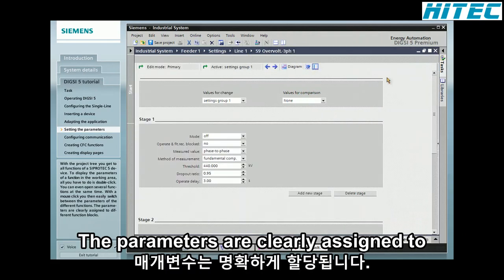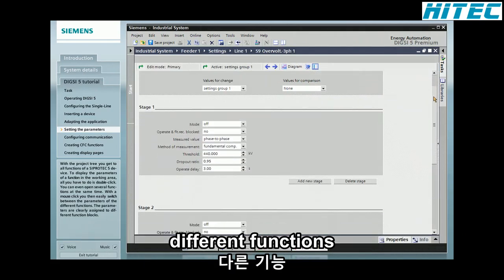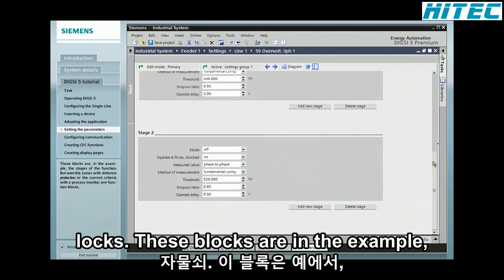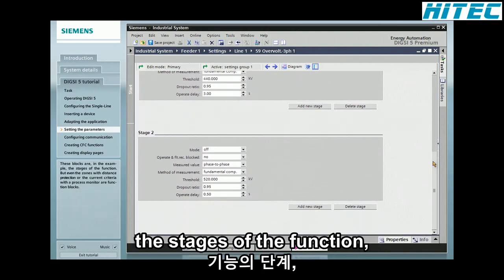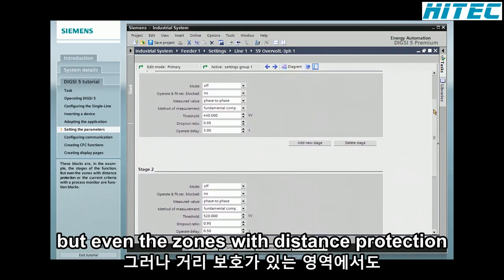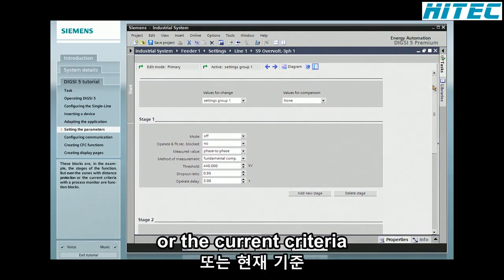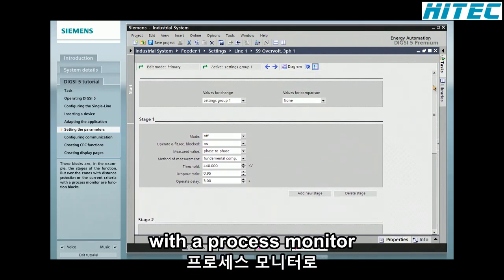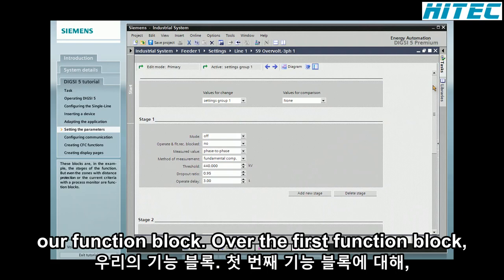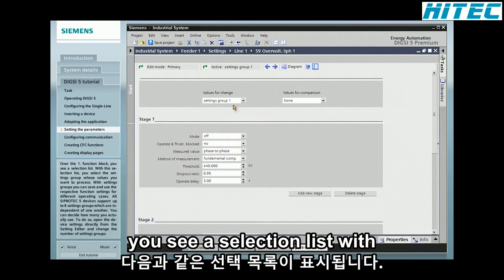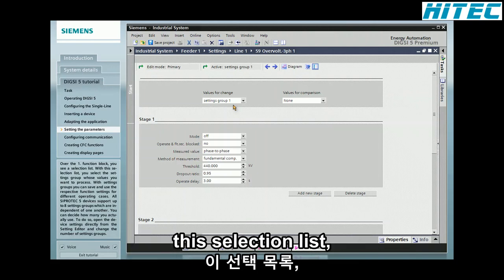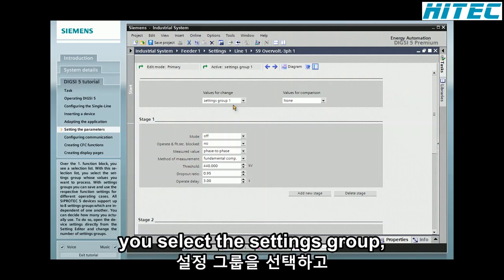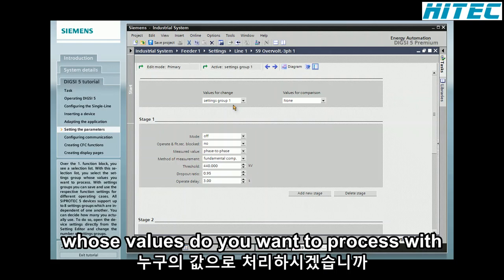The parameters are clearly assigned to different function blocks. These blocks are, in the example, the stages of the function. But even the zones with distance protection or the current criteria with a process monitor are function blocks. Over the first function block, you see a selection list. With this selection list, you select the settings group whose values you want to process.